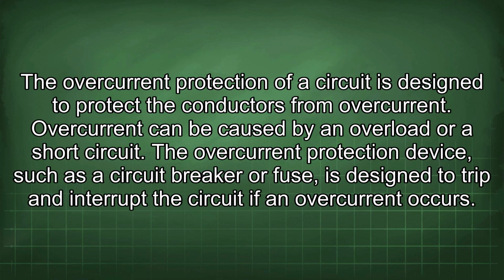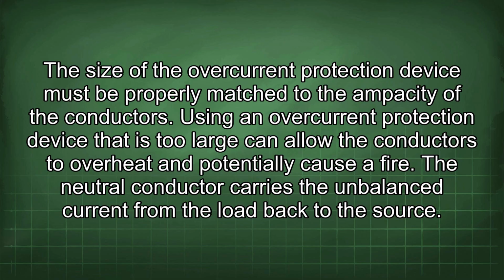The overcurrent protection of a circuit is designed to protect the conductors from overcurrent. Overcurrent can be caused by an overload or a short circuit. The overcurrent protection device, such as a circuit breaker or fuse, is designed to trip and interrupt the circuit if an overcurrent occurs. The size of the overcurrent protection device must be properly matched to the ampacity of the conductors. Using an overcurrent protection device that is too large can allow the conductors to overheat and potentially cause a fire.